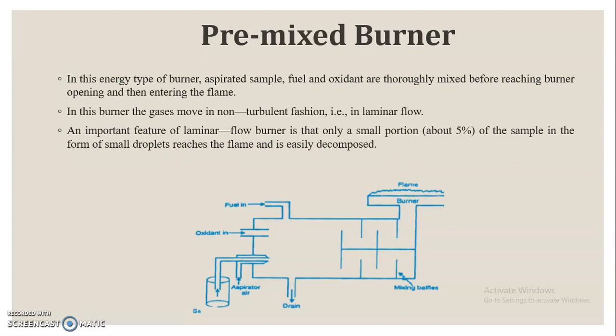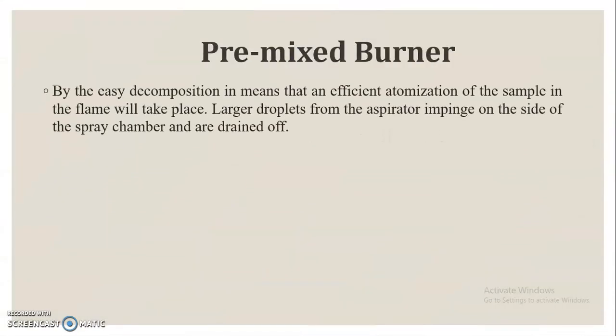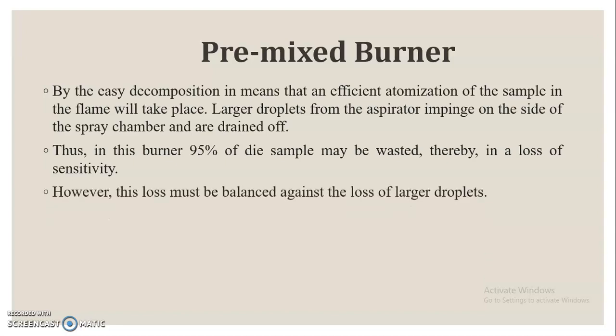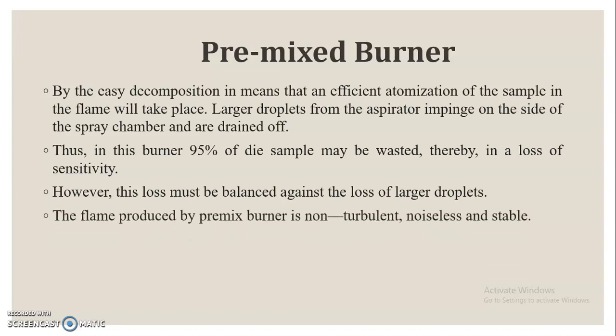An important feature of the laminar flow burner is that only a small portion of the sample, in the form of small droplets, reaches the flame and is easily decomposed. By easy decomposition, it means that efficient atomization of the sample in the flame will take place. Larger droplets from the aspirator impinge on the side of the spray chamber and are drained off. Thus, in this type of burner, 95% of the sample may be wasted, so a loss of sensitivity is observed. However, this loss must be balanced against the loss of the larger droplets.